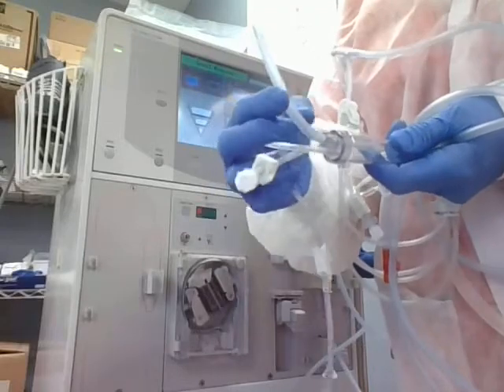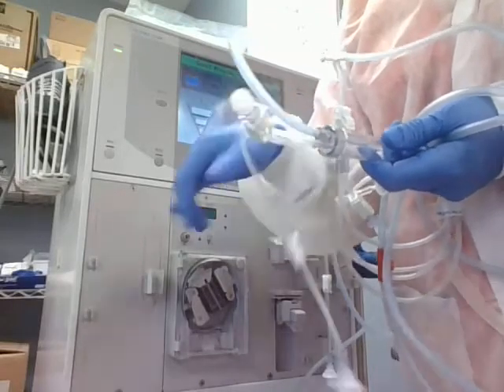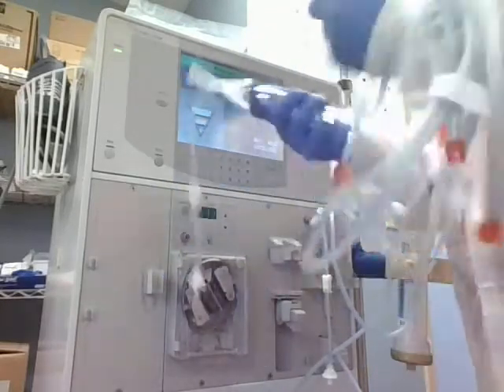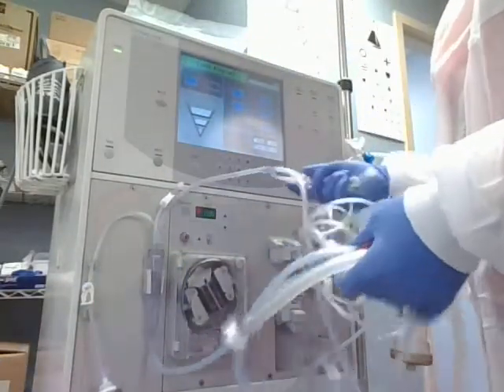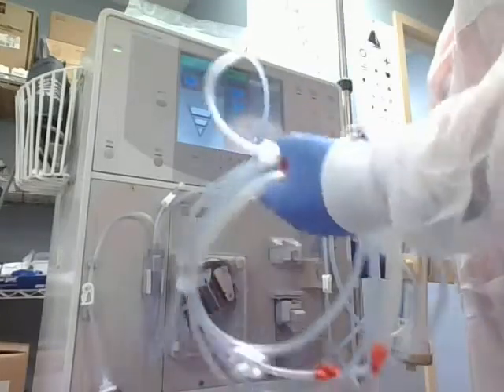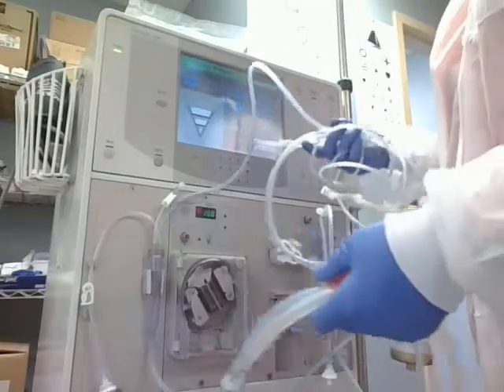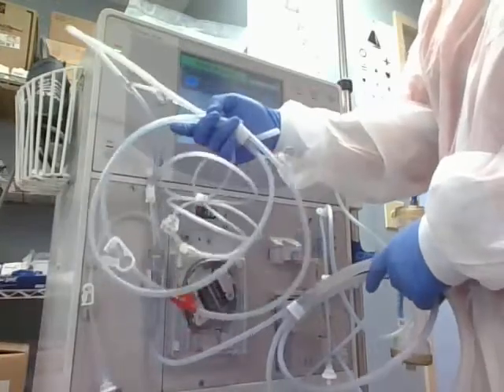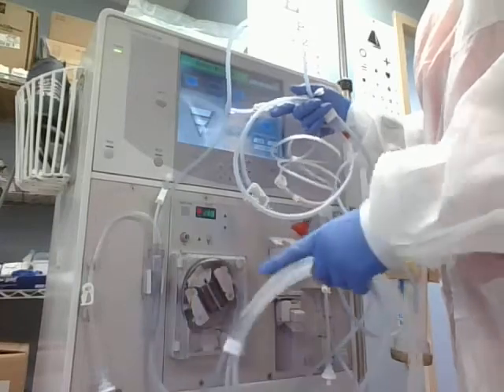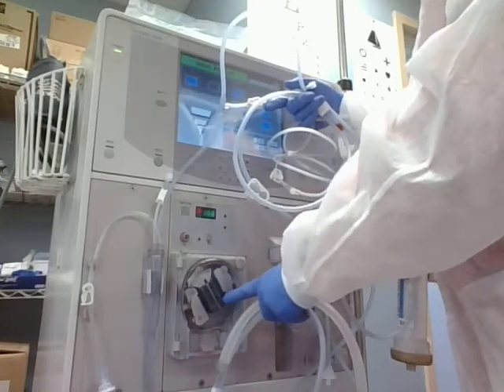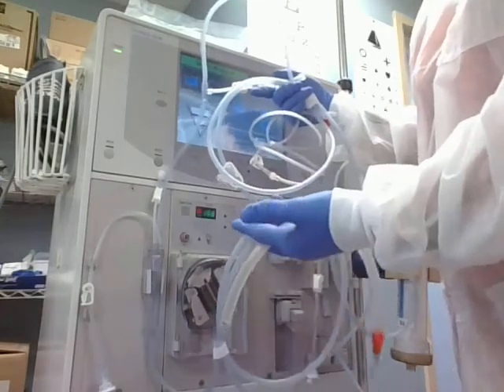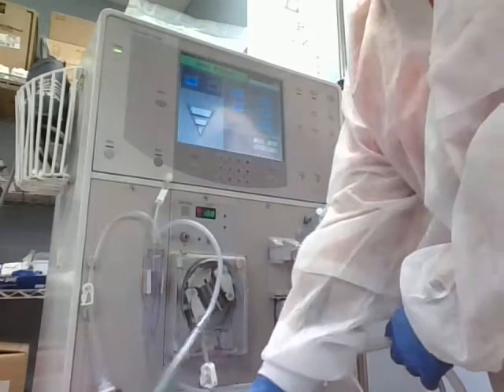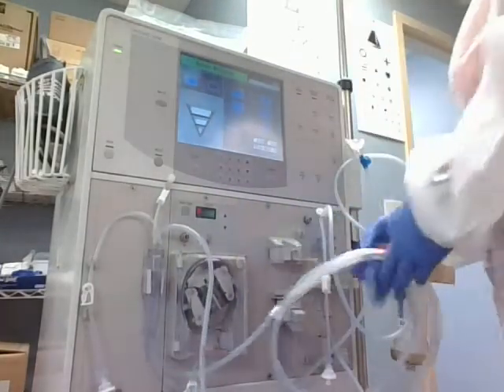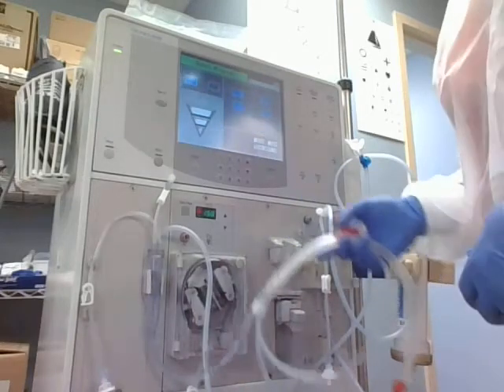Make sure, again, that we're going to put the fat boy to the back. Making sure that that is to the back towards the machine. Okay? Very good. Now, I've got 2 choices here. I can come around and do the saline line, or I can do the tubing, the blood tubing that goes into my pump and has my dialyzer connector on it. So I choose to do my blood pump tubing and my dialyzer connector.